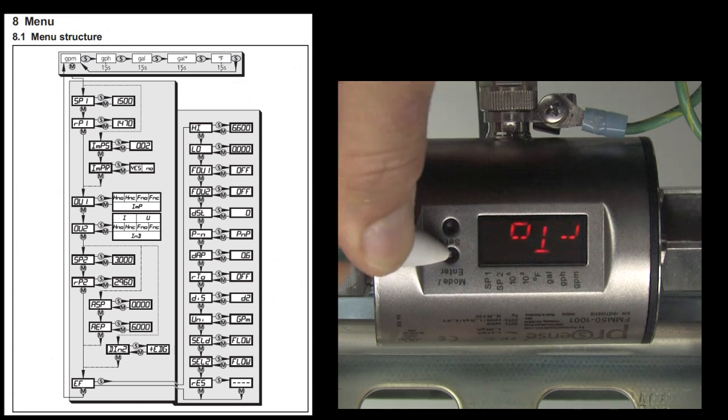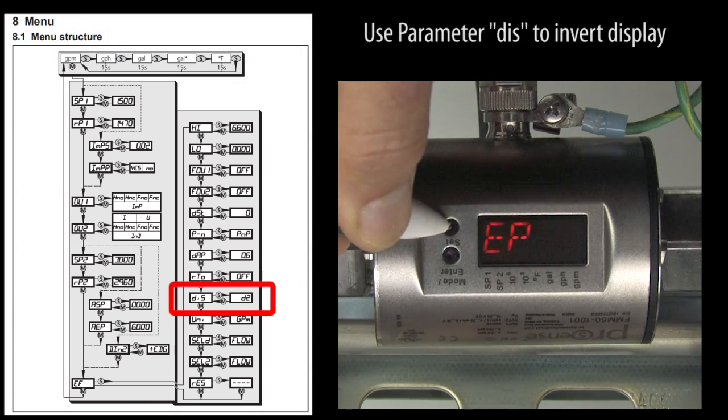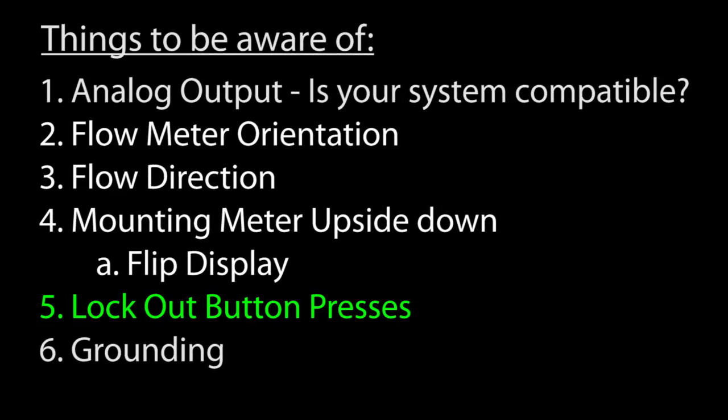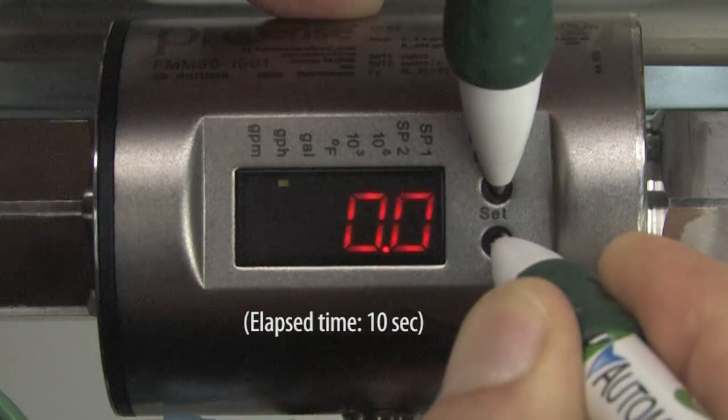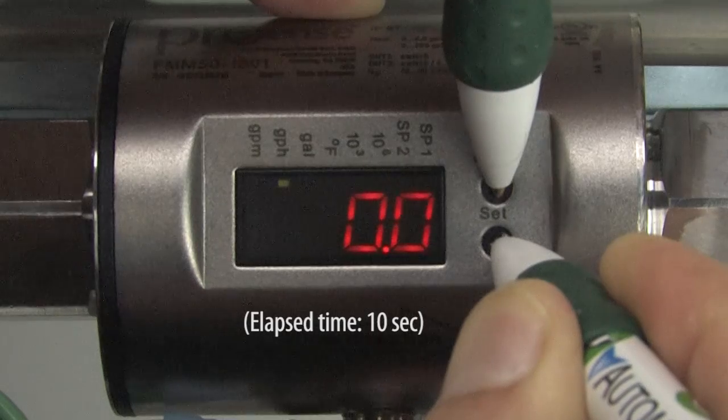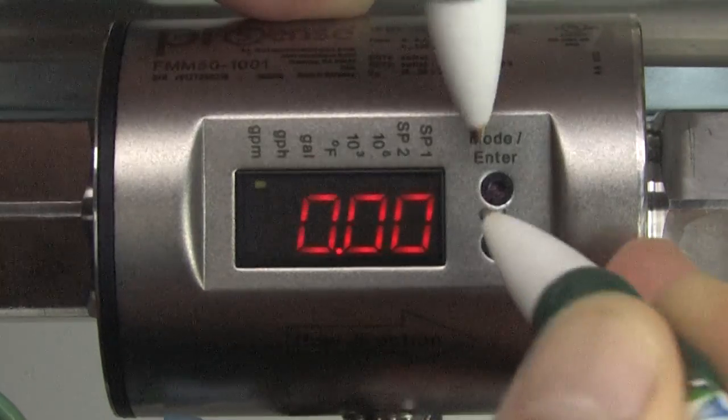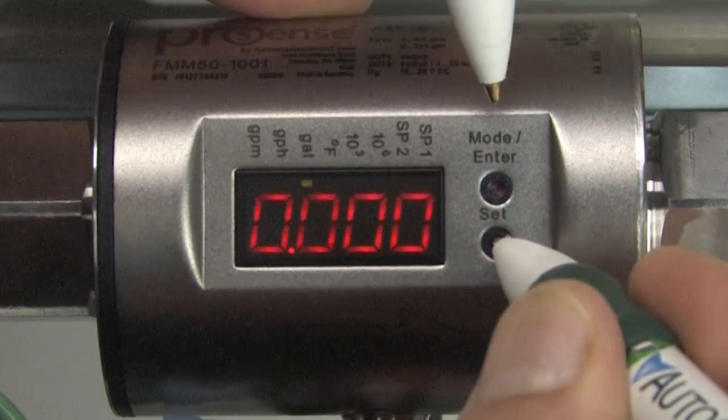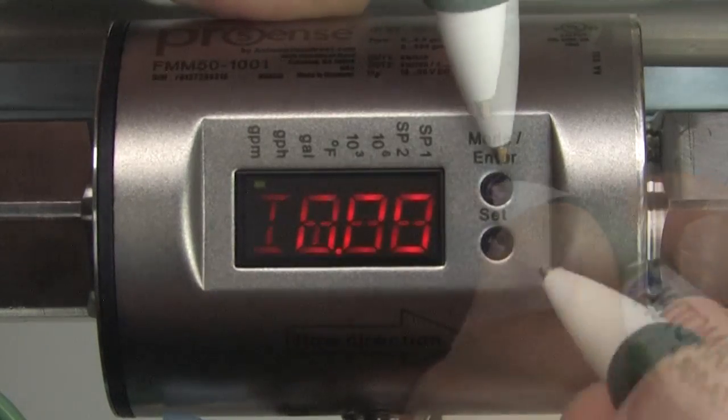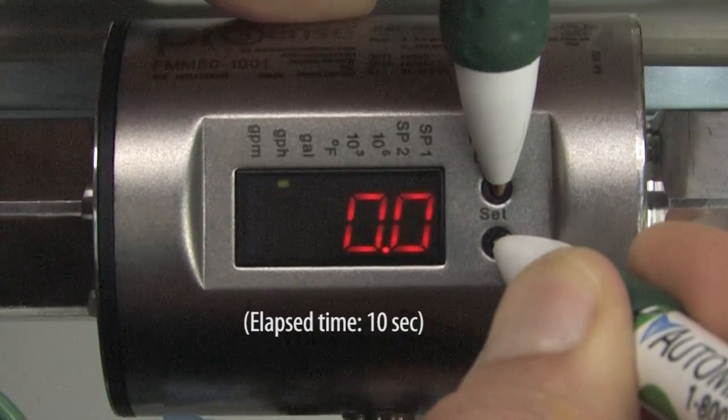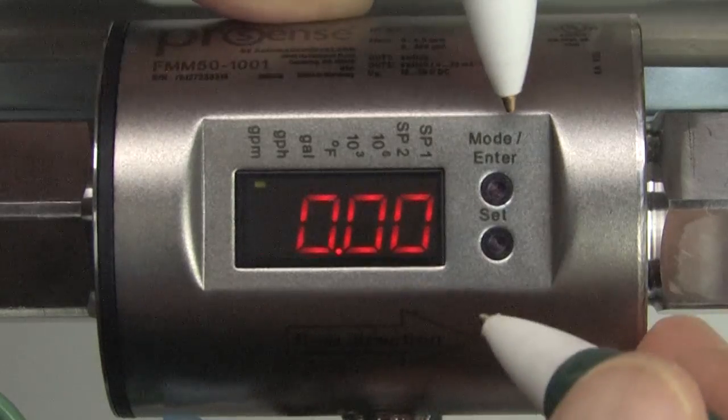You can mount the unit upside down as long as the flow is in the right direction and there's even a parameter you can set to invert the display. You can lock out button presses by holding down the mode and set buttons for 10 seconds. You will still be able to scroll through the menus using the two buttons, but you won't be able to change any of the values. To get control of the buttons back, just hold both the mode and set down for another 10 seconds.